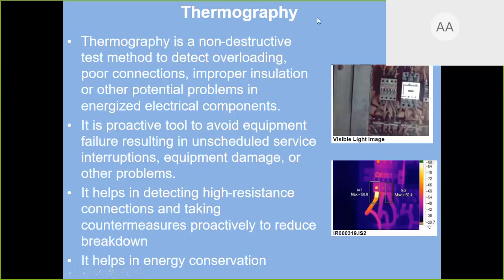There are agencies who do this thermography, you can find out. But thermography will take care of any type of overloading which may lead to fire, poor connection because of spark, improper insulation, or any other potential problem in the energized electric circuit. It is a proactive tool to avoid equipment failure resulting in unscheduled service interruption, equipment damage, or other problems. It helps in detecting high resistance connection and taking countermeasures proactively to reduce breakdown.